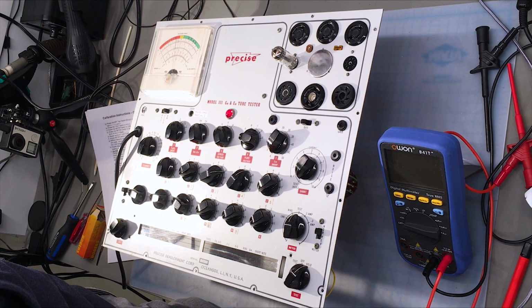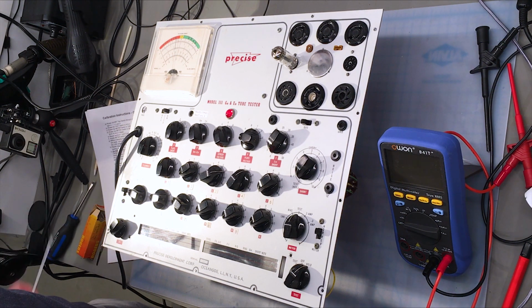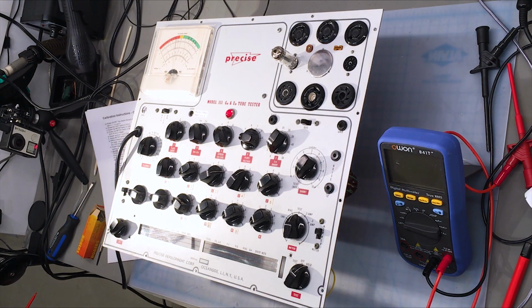If I examine the meter, this is a little more challenging to get a precise reading, but I'm getting a little over 2,400 on the 6,000K scale. So we should be adjusting P5A on the power supply chassis to get the same reading as we had on the 3,000 scale. And so we'll adjust P5A.